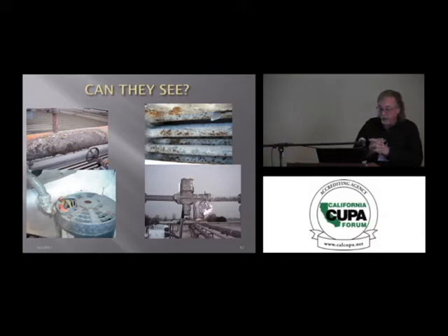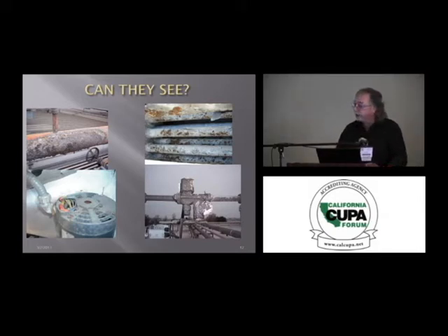Okay. Other things that you should look for naturally is just simple things. Corrosion on the outside of pipings. One of the biggest areas we find corrosion is by our condensers. We treat our condenser water with chemicals, and then sometimes we have some overspray and that lands on the piping. And this one on the left-hand side top there is one that's running along the top of a condenser. And then, of course, the one on the bottom left, that's simple. It's open electrical. We find that all the time.